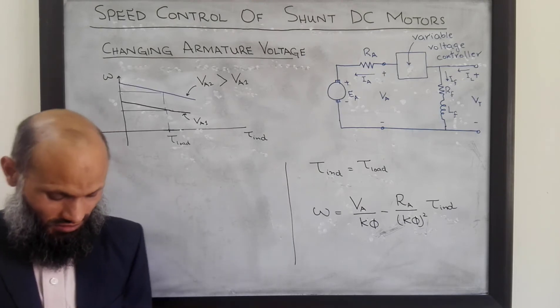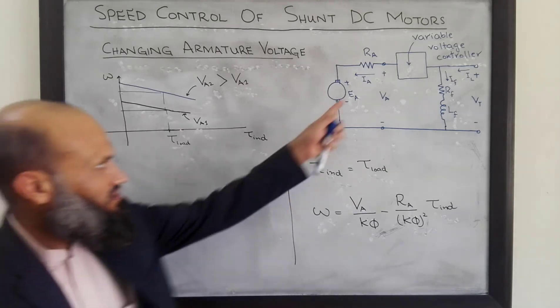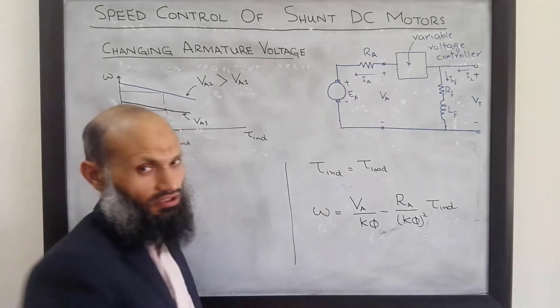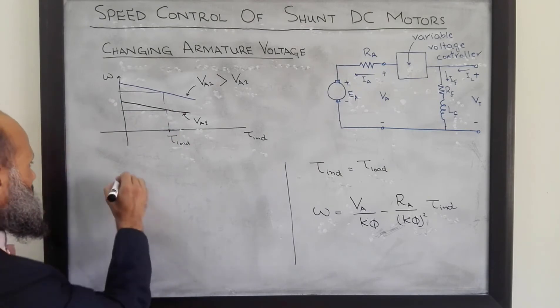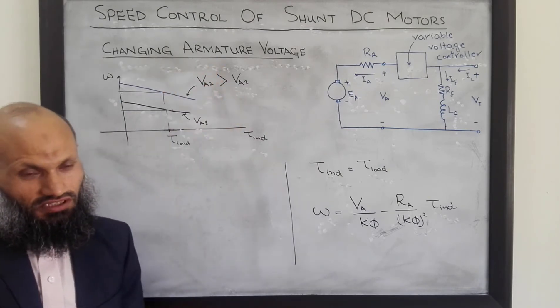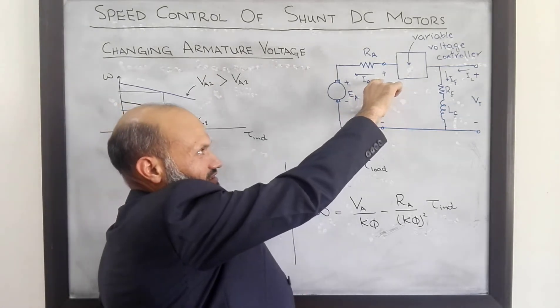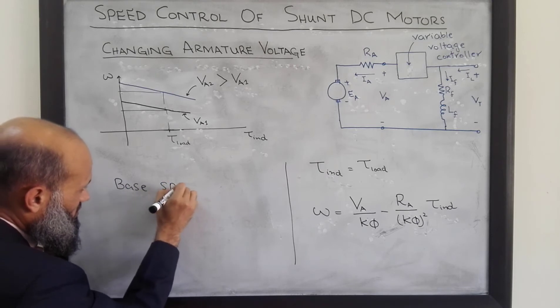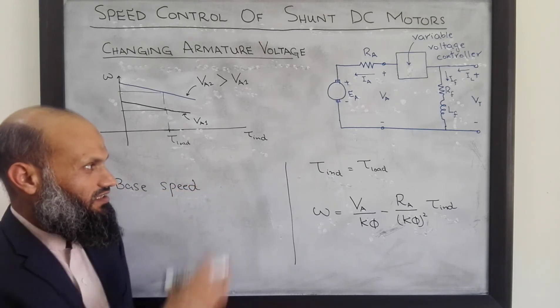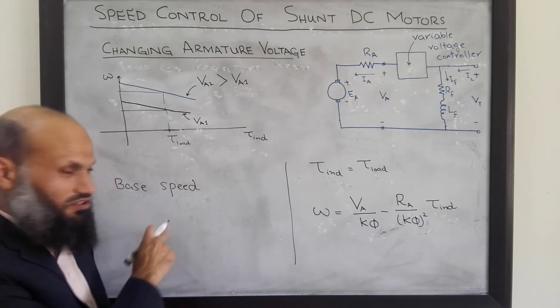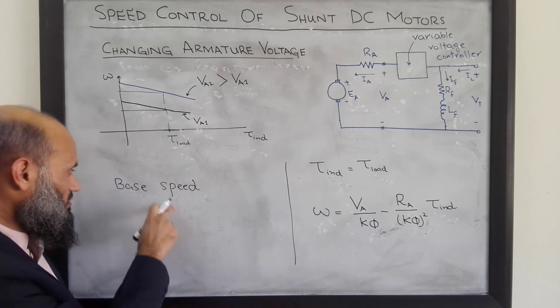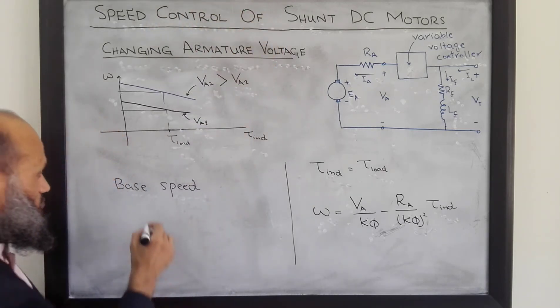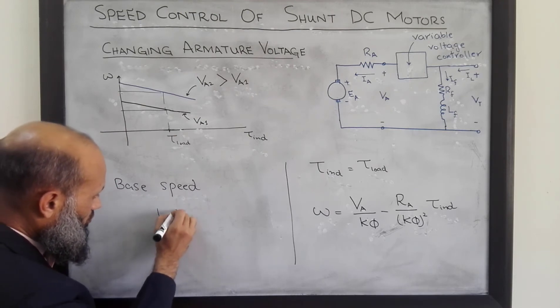A precaution with this approach: the armature windings can handle only a particular amount of voltage. If excessive voltage is applied, the insulation of the windings may get damaged. Therefore, this approach is limited by the maximum voltage that can be applied to the armature winding. Base speed is defined as the speed of the motor when rated voltage and rated load are applied, and this technique can only be used to control speed below the base speed.